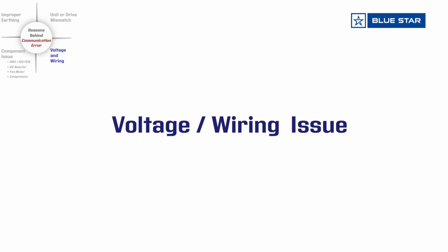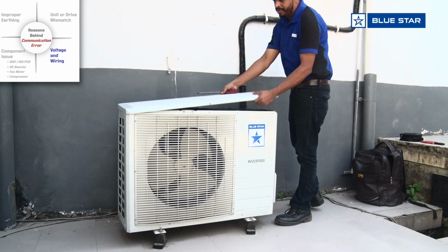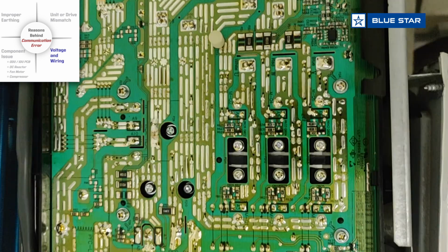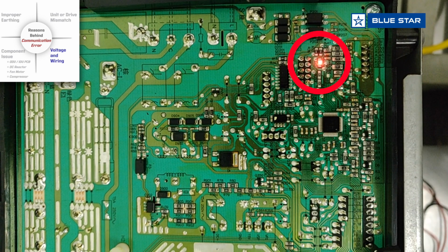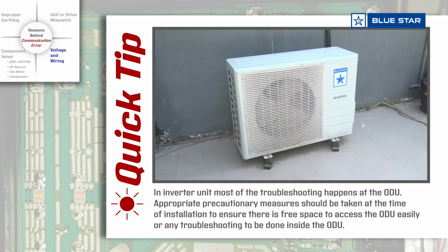If communication error is not because of unit mismatch, then dig more into components failure issue. To do that, first open the ODU cover and locate the LED on the PCB. This LED gives us direction for further diagnosis. Quick tip: in an inverter unit, most of the troubleshooting happens at the ODU. Appropriate precautionary measures should be taken at the time of installation to ensure there is free space to access the ODU easily for any troubleshooting to be done at the ODU.